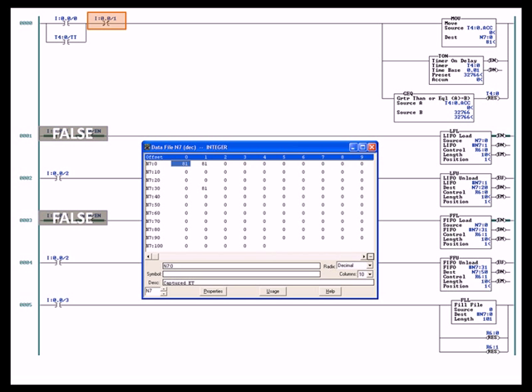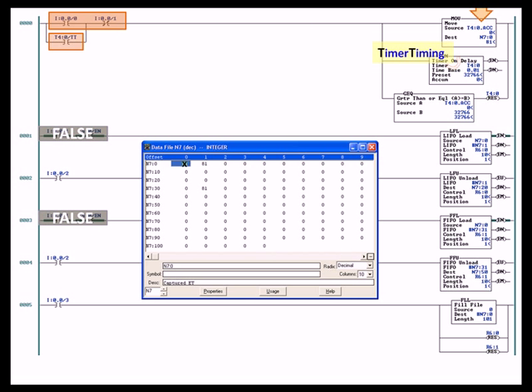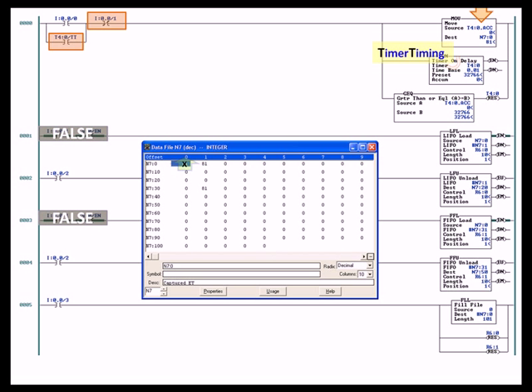Now when you flip input 0 on, then that instruction goes true, the rung goes true, the timer starts timing, and the timer timing bit bypasses the switch 0 to keep the rung true. So as long as this rung is true, the timer is going to continue to accumulate.